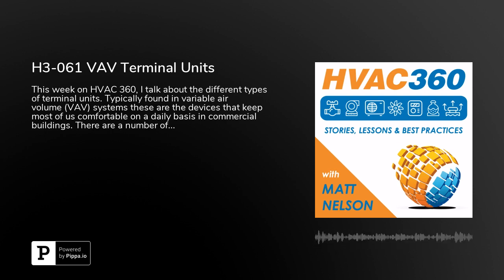The only other box, actually, I did find a new box that typically I've thought of as more of a hospital unit, but they're induction units, and they kind of put it after the fan-powered boxes because they use the Venturi effect, and it actually induces the plenum air into the device to mix it there. So those are some of the boxes that are more typically used. Again, the straight single duct boxes and the fan-powered boxes are probably the more popular boxes that you're going to end up running into, and their uses.